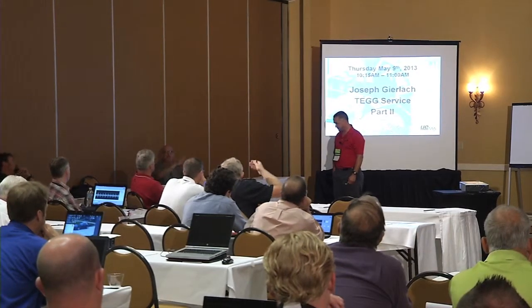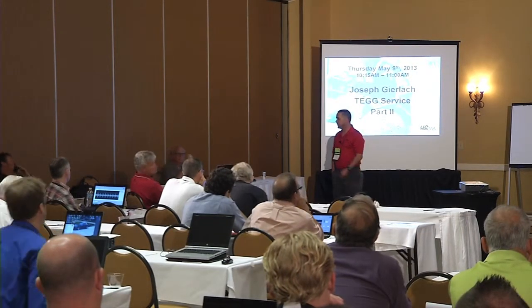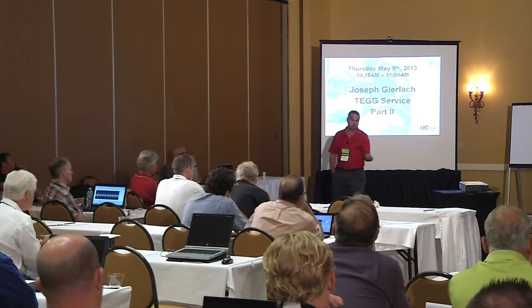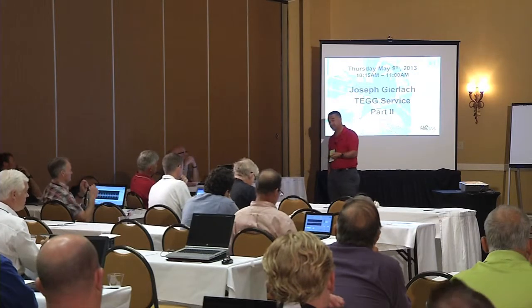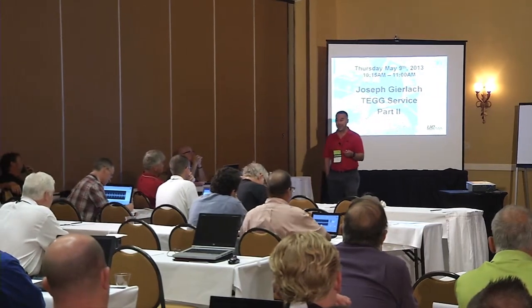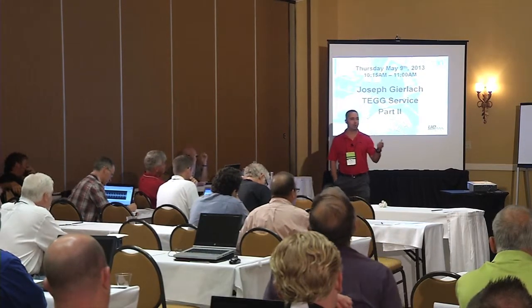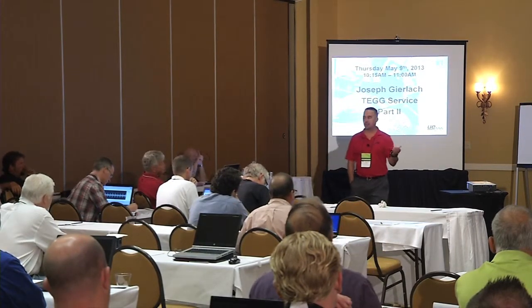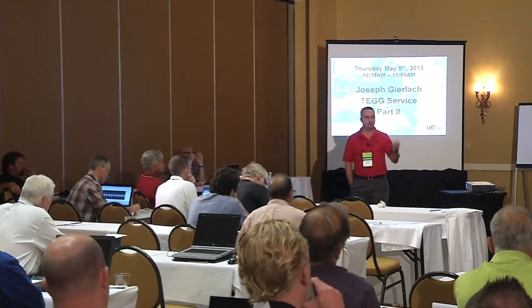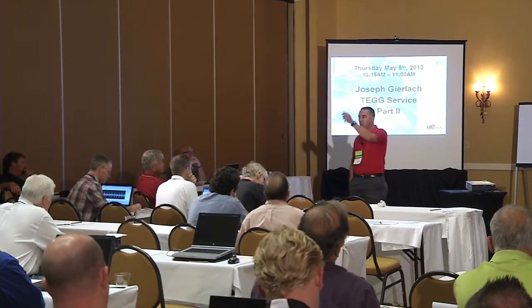It's based upon that harmonic, not 60. That makes sense, for the switching speeds of the devices, right? Right. And a lot of the local oscillators are at 40 kilohertz, that I've seen. But yep, no problem. So mechanical, we talk about mechanical, it may be a problem, it may not be a problem. 50 and 60 cycle hum to me is a mechanical issue. It's evidenced by the harmonics being all across the spectrum, but the lack of frequency noise. Does that make sense? All right.